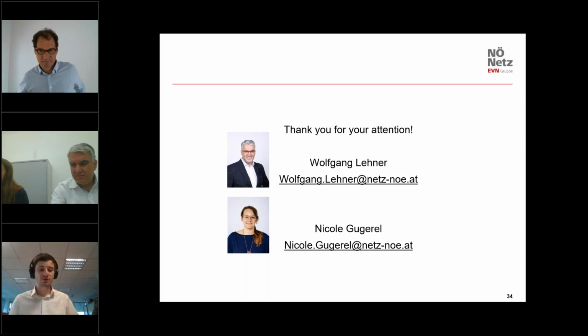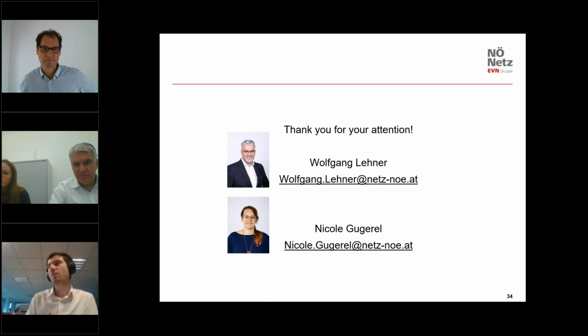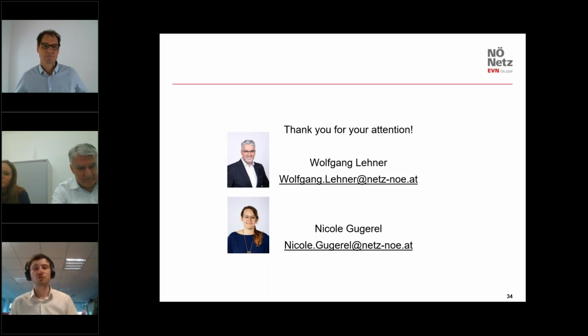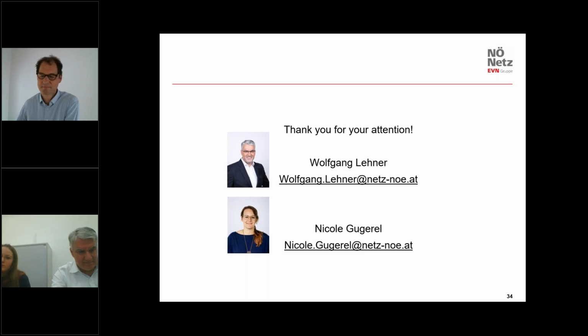Yeah, so we have a procedure for this case. We try to have less than 0.5% of meters without communication in the last 2 months - this is one of the KPIs. For those that reach these 2 months, we try to operate remotely, and if we can't get the index, we try to call the customer, or go on the field to check the meter. If needed, we replace the meter if we think it's not a PLC issue.